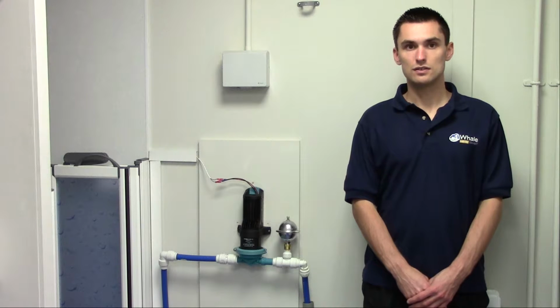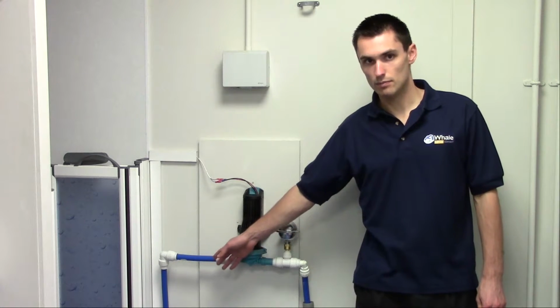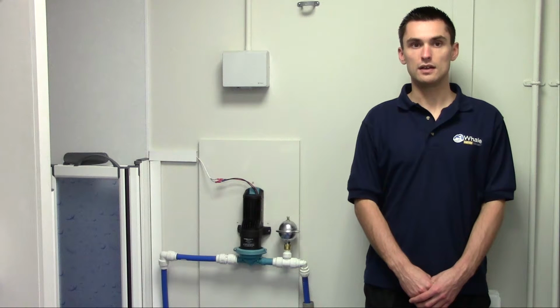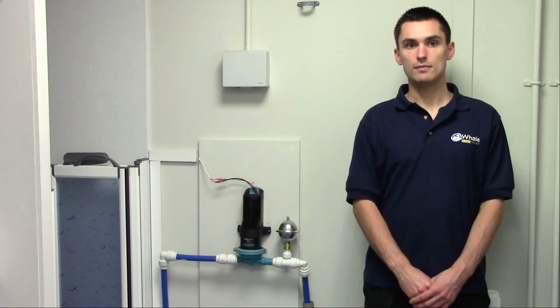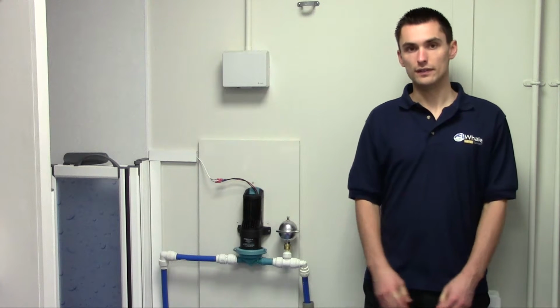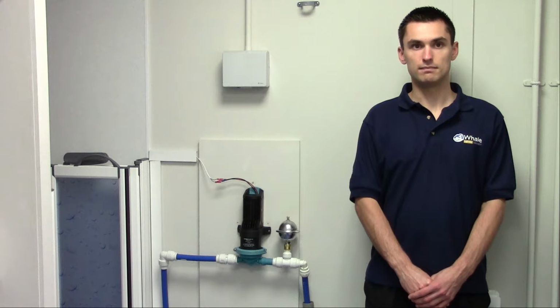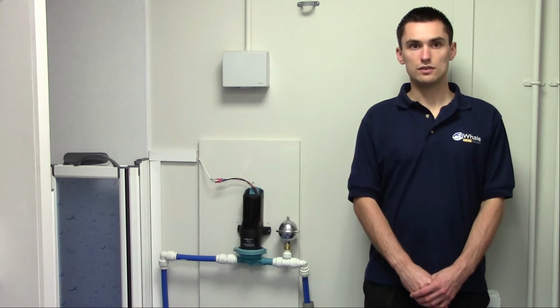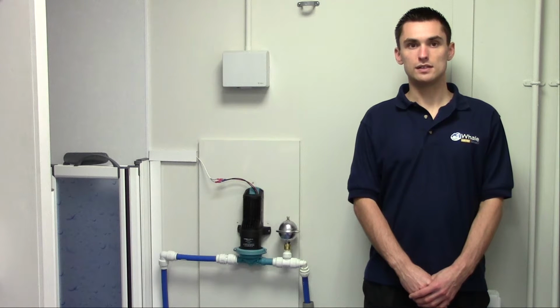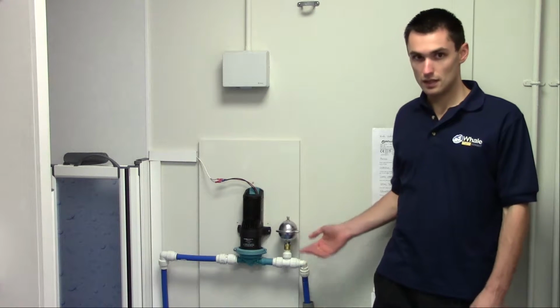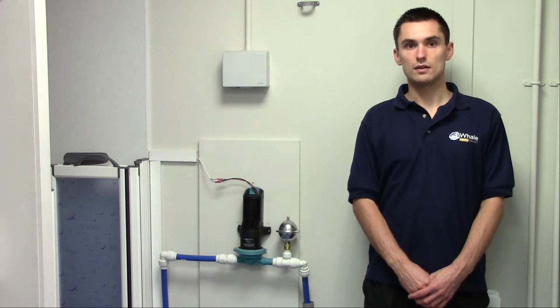Either side of the pump we have 22mm pipework connected to the pump using push-fit style fittings for ease of access. On the inlet side of the pump it can pull a maximum of 2 meters from the gully on the horizontal and lift half a meter vertical. On the outlet side, the pump can pump another 1 meter in height. Formed bends must be used throughout the pipework and the pipework needs to be secured in place. The use of this surge damper is to reduce potential for water hammer in the pipework.